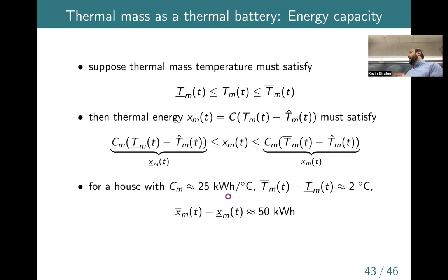So if you're doing something fast like that, using the fast battery in a building, the air temperature, kind of makes sense. And those signals tend to be zero mean over time. The grid is always sloshing around, 59.9, 60.1 or whatever it is, so you're ramping up as much as you're ramping down. The temperature signal just looks like noise around the set point, which is what temperature looks like anyway. With thermostatic control, we see this zigzag with a period on the order of maybe 15 minutes. So it's totally normal, and it's basically imperceptible, is the argument. Whether it is or not is up to the building occupant. We'll see. But that's one thing: providing these fast time scale services for reliability purposes.